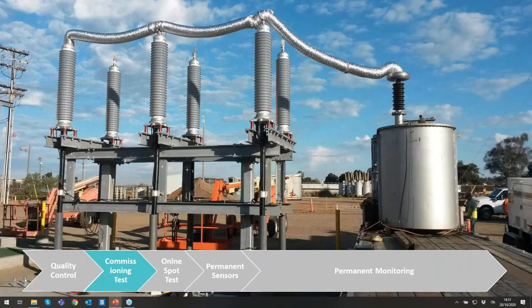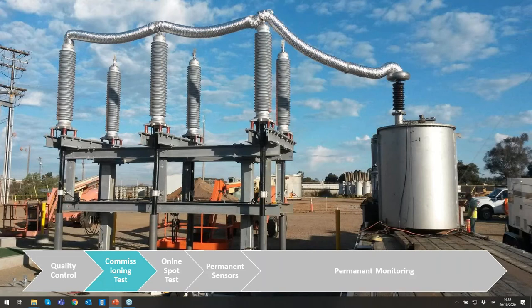Moving to the second part of the life of the cable: both high voltage cables and high voltage accessories have successfully passed all the quality checks at the factory. They are then shipped on site, the cable is pulled into cable trays or tunnels, and different sections are jointed together with accessories. At the two ends we have outdoor terminations, transformer terminations, or GIS terminations. This introduces new possible sources of defect, since preparing joints and terminations is almost a craftsman job, and mistakes can induce partial discharge phenomena in such accessories.